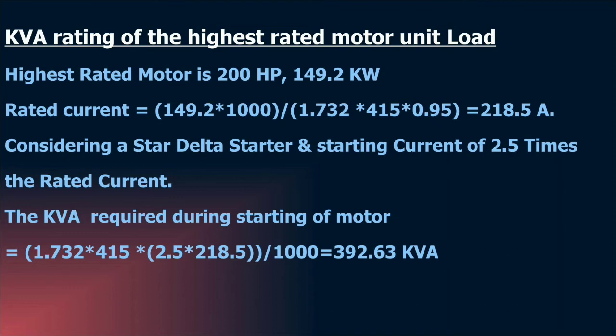We are assuming that a star delta starter is used for starting this motor. So the initial inrush current will be approximately 2.5 times the rated current. Now we can calculate the kVA required during the starting as root 3 VI, which is the same as 1.732 into 415 into 2.5 into 218.5 divided by 1000, which is the same as 392.63 kVA.